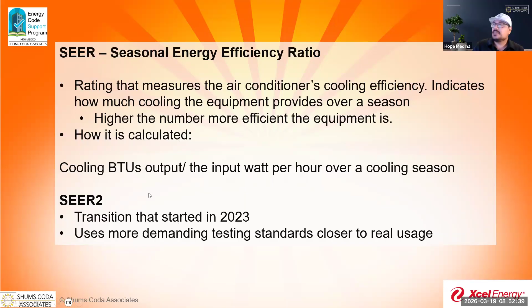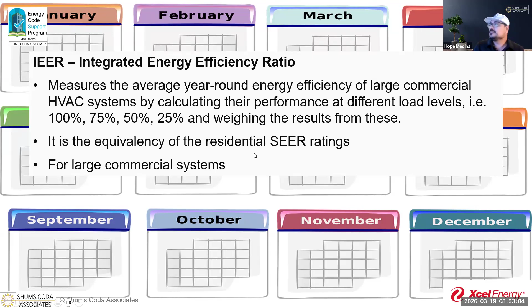IEER is integrated energy efficiency ratio, and that's looking at the average year-round energy efficiency for commercial systems at their different load levels, 100%, 75, 25, 50, etc. And it's equivalent to the SEER ratings for residential, but they're looking at it from a different paradigm there. So this is what applies when we're talking about our large commercial systems.